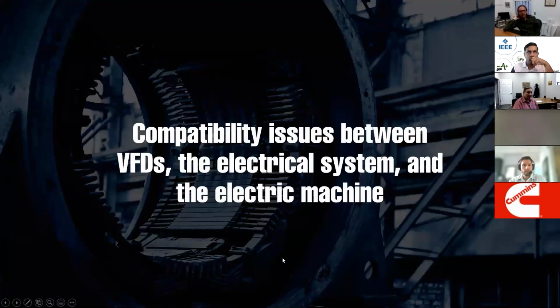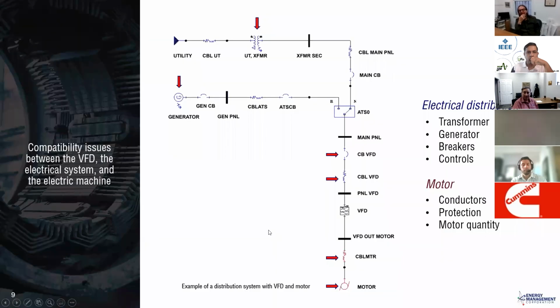So what we're going to focus on here for the next 10 or 15 minutes are compatibility issues between the VFD, the electrical system, and the electrical machine or machines. You could even have multiple machines on one single drive. And look at it from an electrical distribution standpoint. You've got the utility here, which certainly has something to say regarding non-linear loads coming back into them. That's usually measured at the utility transformer or the point of common coupling on the primary side. So we'll talk about each of these points where there could be an interaction of compatibility challenges.